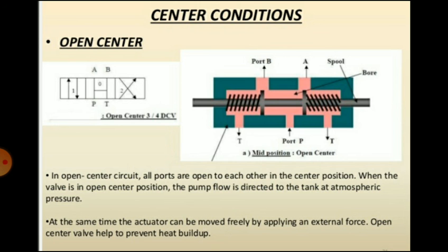When the valve is at center position, the pump flow is directed to the drain through the valve. The other two positions are to reciprocate the cylinder. In open center position valve, since the fluid is directly drained, no heat is built up in the fluid and no work is done by any part of the system.